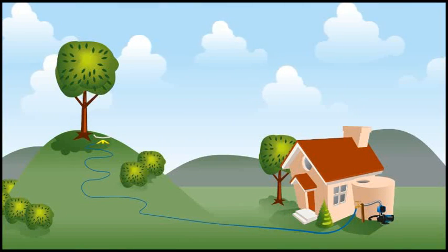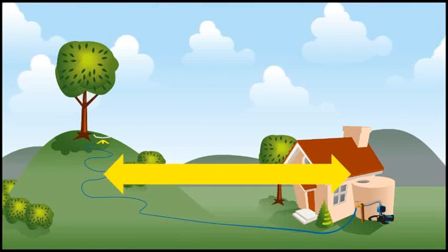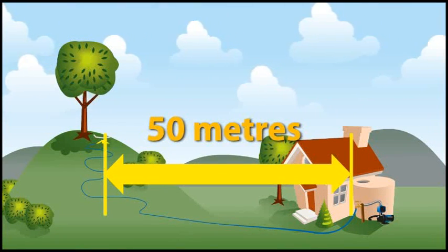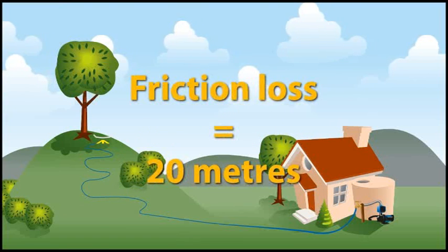In Aunty Flo's case, she only requires 50 metres of pipe, therefore we must halve the value. Half of 40 is 20. 20 metres is therefore our friction loss.